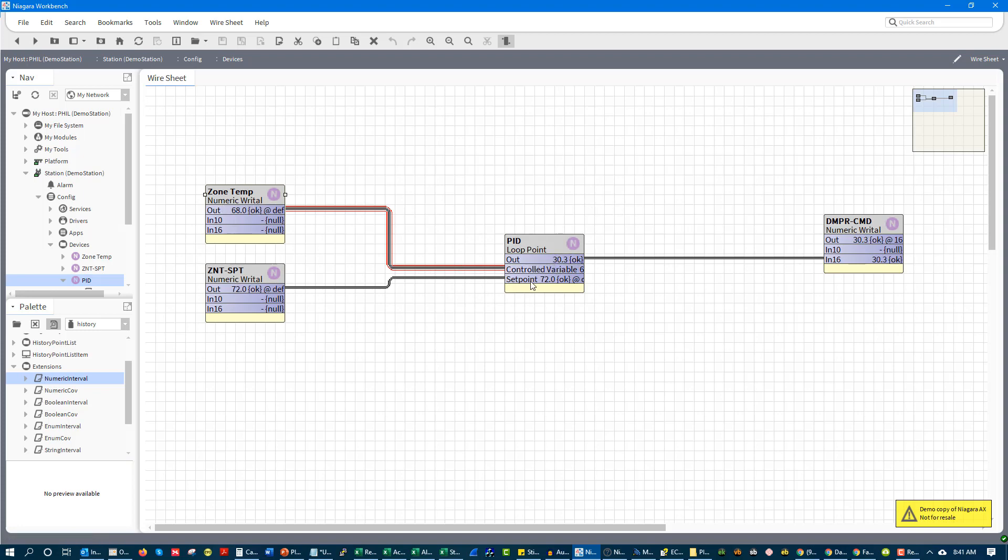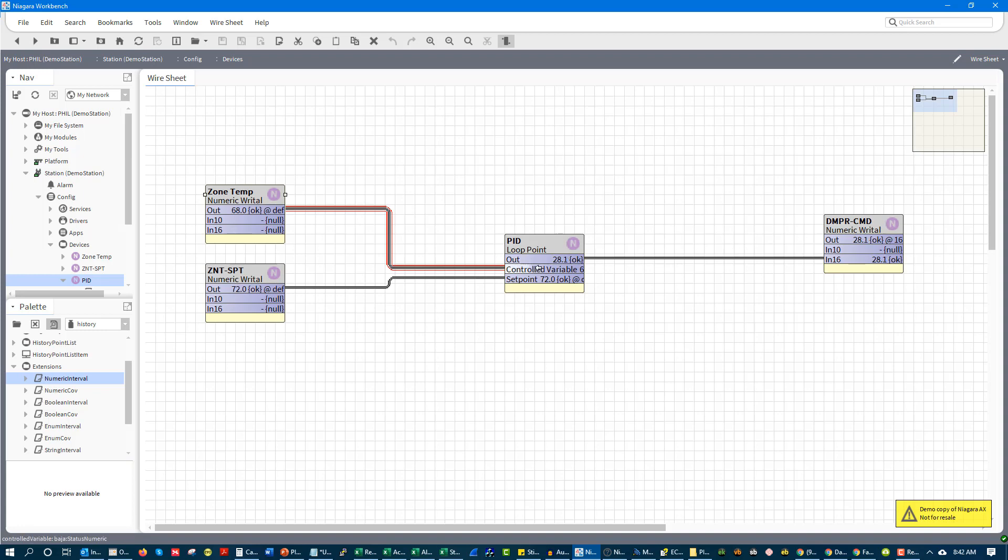But we're going to see I start getting really fast. It's ticking down pretty quick now. And so this is what you want to have happen. You want your proportional band to respond accordingly. That's going to initially load the output of your PID loop. And then you want your integral to start building up over time the longer you have this error.